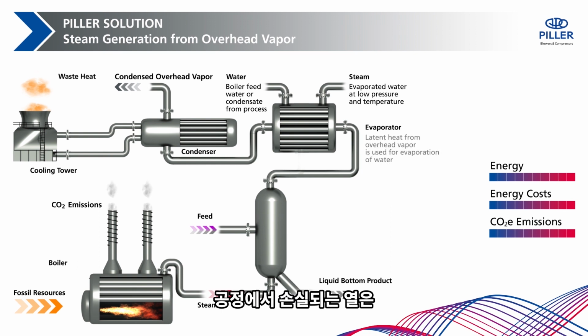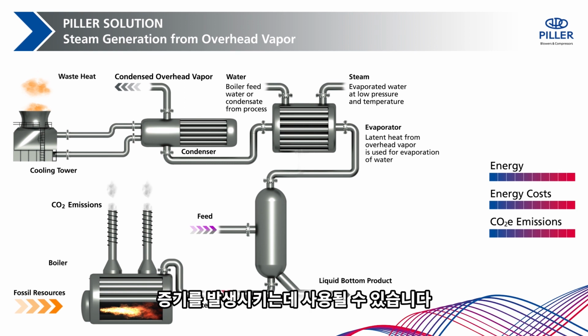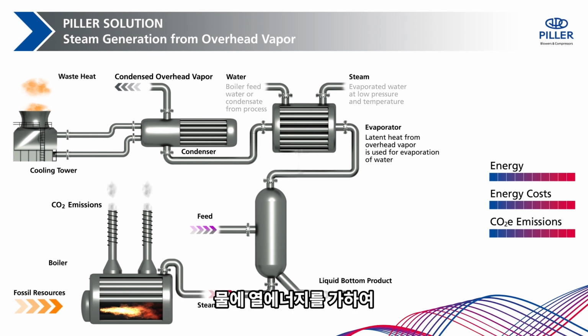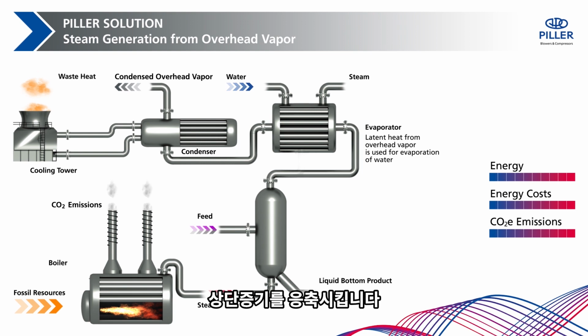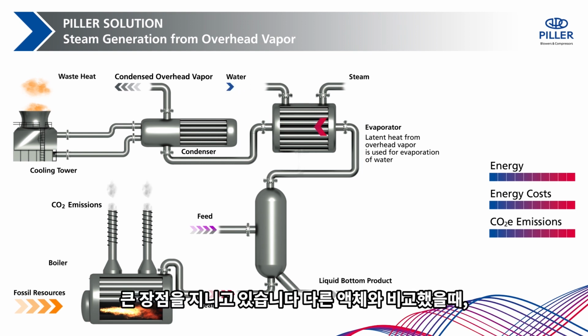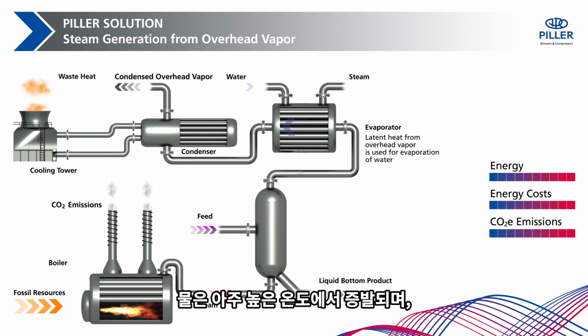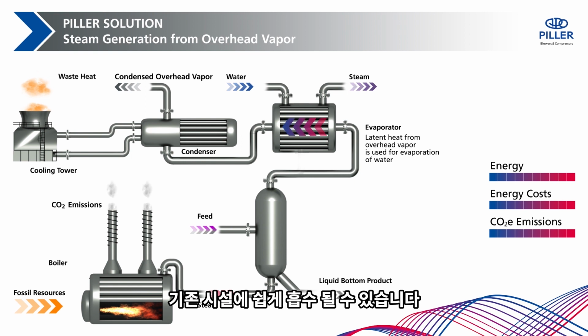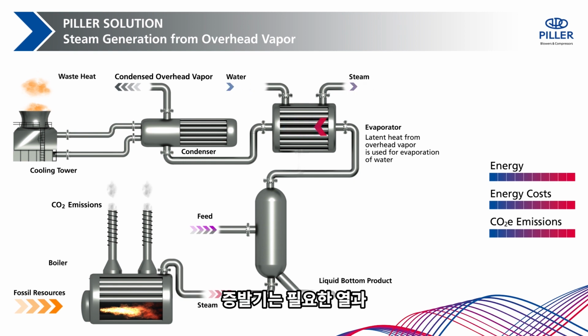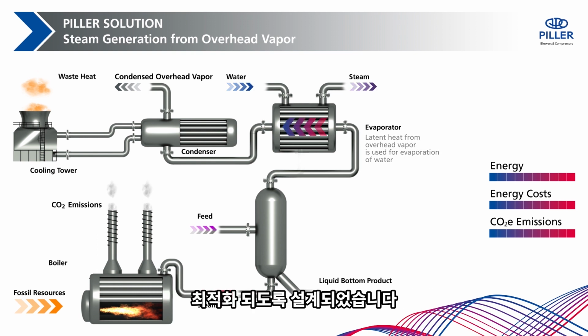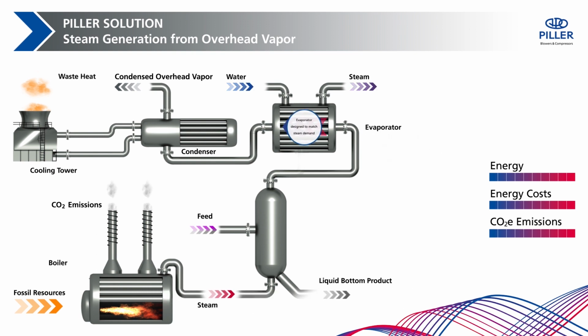Process waste heat is used as heat source for generating the steam. The thermal energy is transferred to the water condensing the overhead vapor. This form of heat transfer has major advantages. Compared to other fluids, water has a very high heat of vaporization and can be integrated into the existing infrastructure. The evaporator is specifically designed to meet the required heat demand and process conditions, defining the mass flow and temperature of the generated steam.